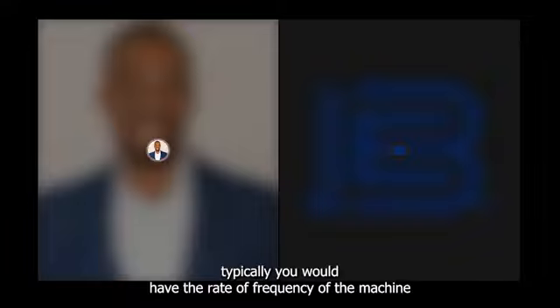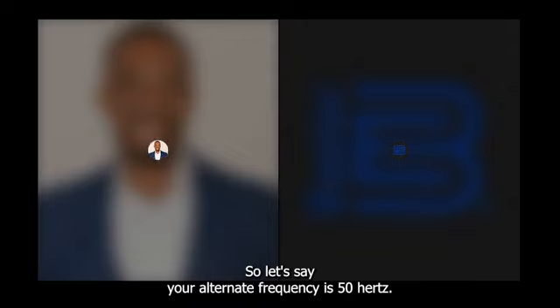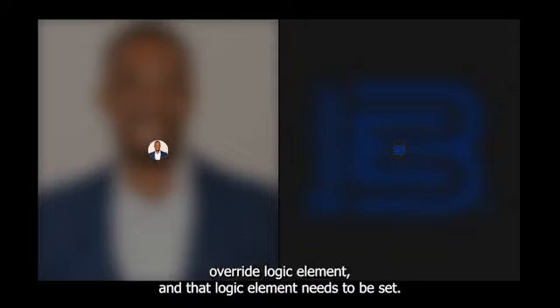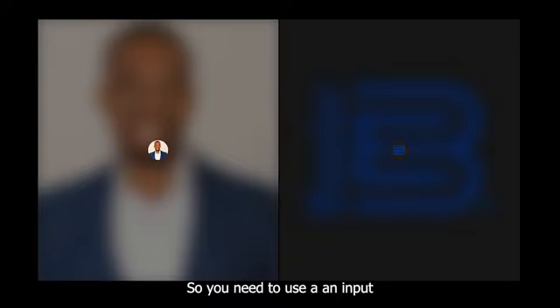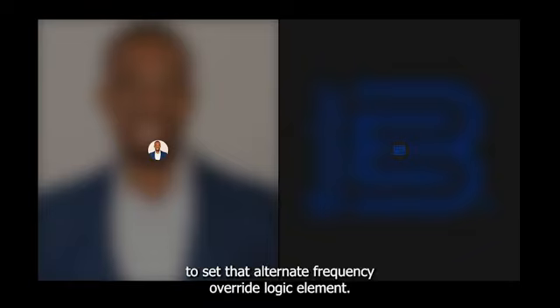Okay, so typically you would have the rated frequency of the machine, and in a US-based application, that would be 60 hertz. And then you need to have the alternate frequency setting. So let us say your alternate frequency is 50 hertz. Then there is an alternate frequency override logic element, and that logic element needs to be set. So you need to use an input to set that alternate frequency override logic element. Let's say you use a contact input.